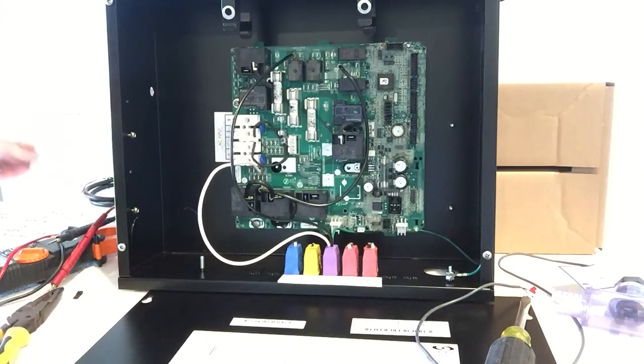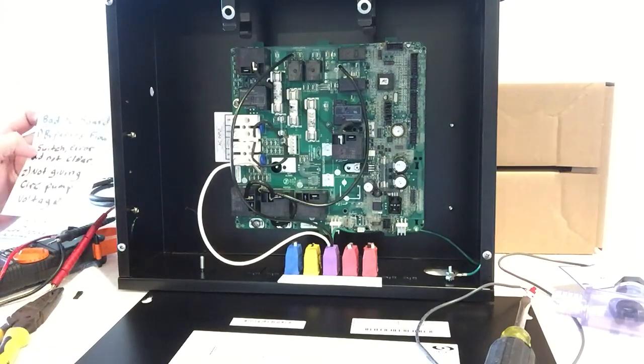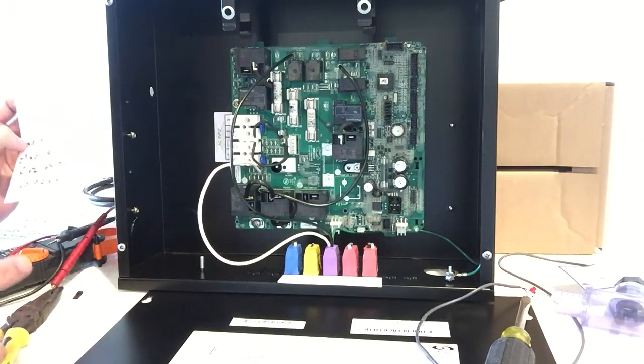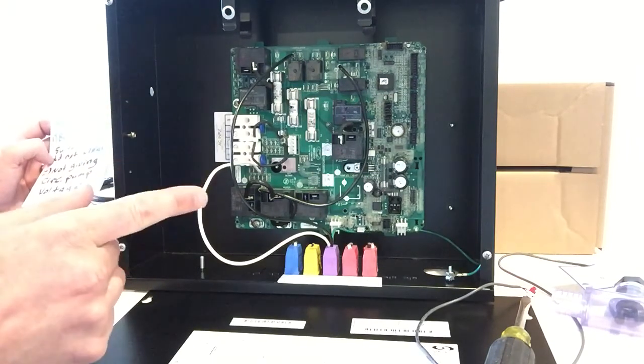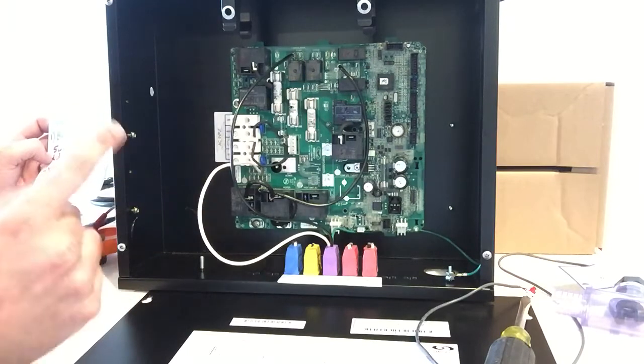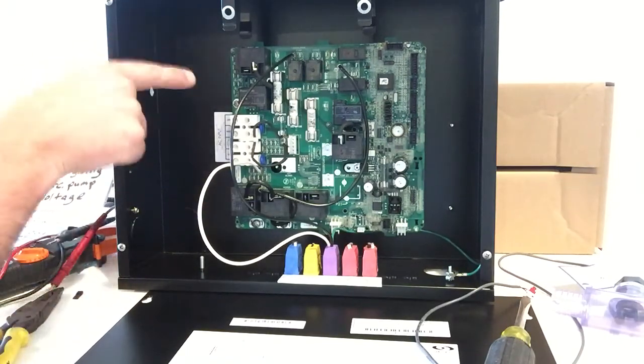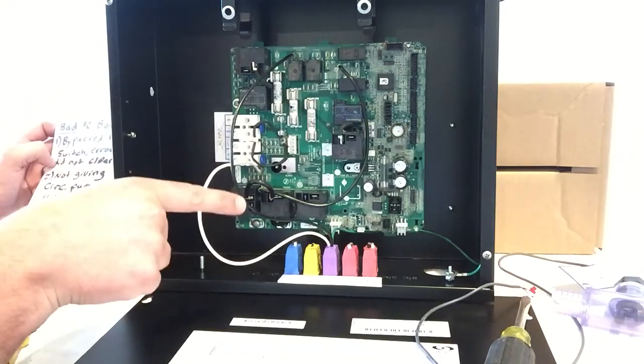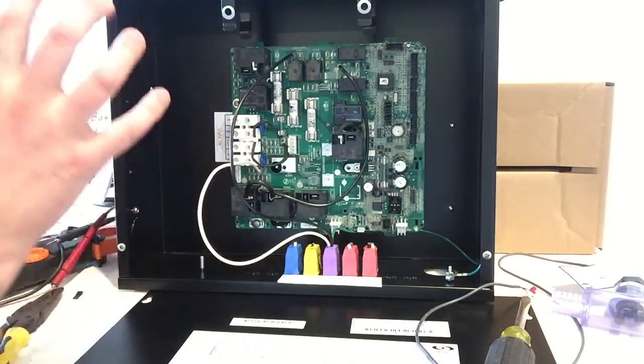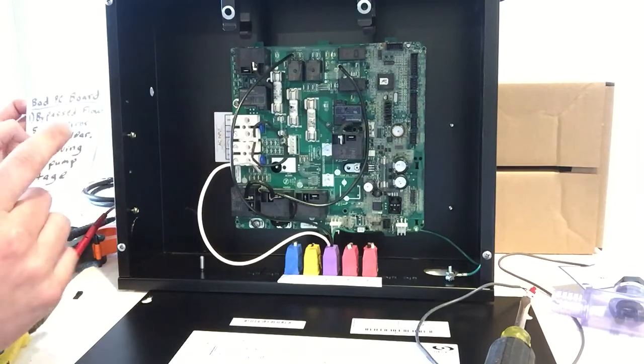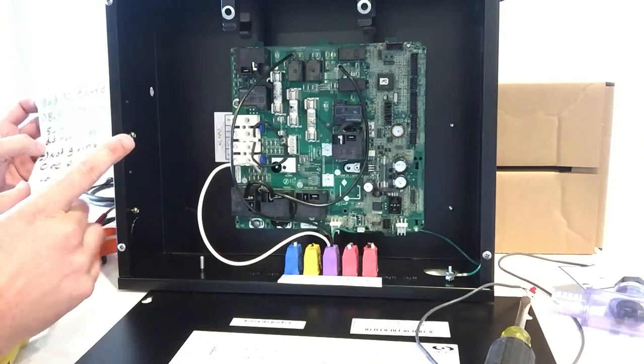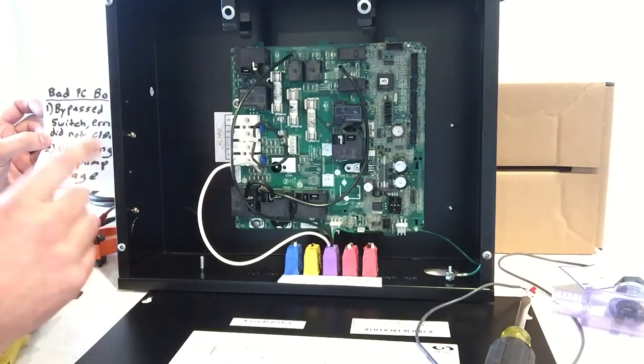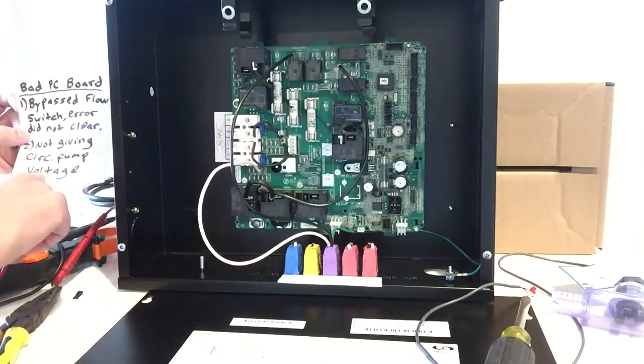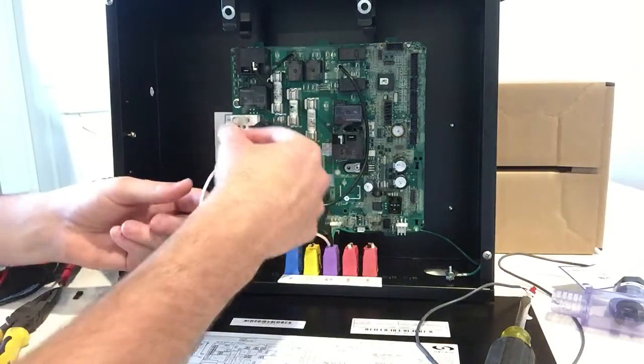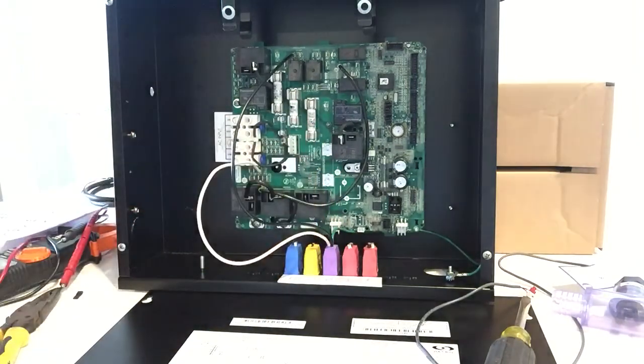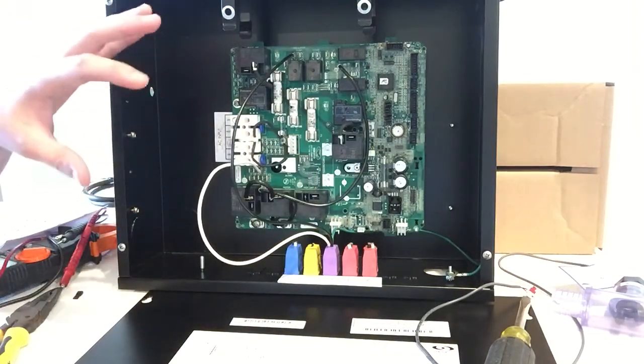So, if your circ pump runs fine, you bypass the flow switch and the error still remains there, your PC board is bad, because bypassing the flow switch with the pump running, it should automatically clear the message. So that's case number 1 for a bad board. Also, if your flow switch is good and your board is not giving the circ pump the correct voltage, then the PC board is bad.